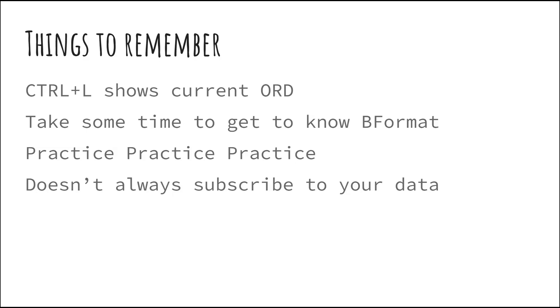If a component doesn't have a way to subscribe to your data like a history extension, the data in the BQL is only going to update when you're looking for specific things — such as a component directly rather than a folder. If you change it to a component it will constantly update, so be careful about how you format your queries. That's all for today about Baja Query Language. Watch for a follow-up video outlining other types of queries, and contact me with any questions at charles.johnson@linkspring.com. Thank you and have a good day.